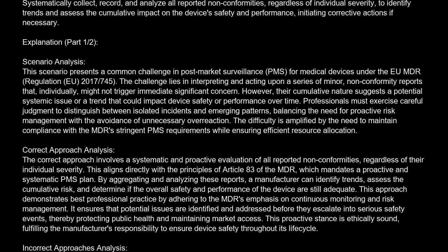Explanation. Scenario analysis. This scenario presents a common challenge in post-market surveillance (PMS) for medical devices under the EU MDR regulation, EU 2017/745. The challenge lies in interpreting and acting upon a series of minor nonconformity reports that, individually, might not trigger immediate significant concern. However, their cumulative nature suggests a potential systemic issue or a trend that could impact device safety or performance over time. Professionals must exercise careful judgment to distinguish between isolated incidents and emerging patterns, balancing the need for proactive risk management with the avoidance of unnecessary overreaction.